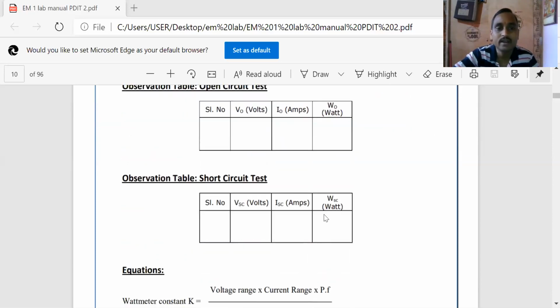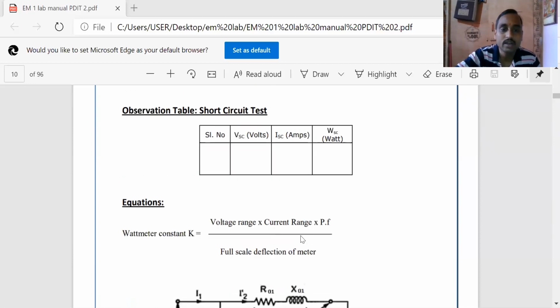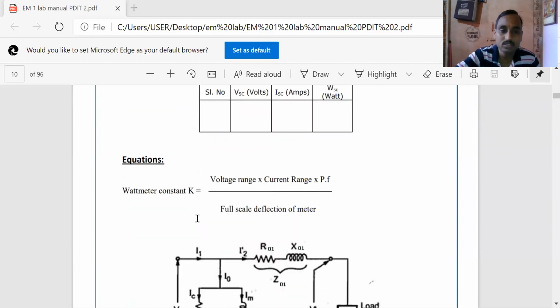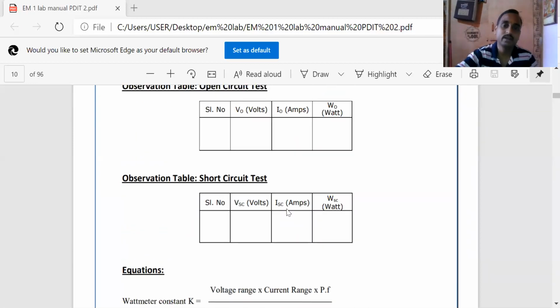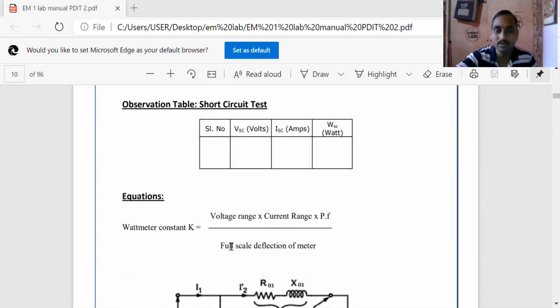Okay, and for the short circuit test, we will call it VSC, that is called the short circuit voltage. ISC is called the short circuit current, and WSC is called the short circuit power. The same voltmeter, ammeter, and wattmeter readings will be taken under the short circuit test, and calculate the wattmeter constant. So in our laboratory, we are using a multifunction meter. So if you use the multifunction meter, no need to find out the wattmeter constant.